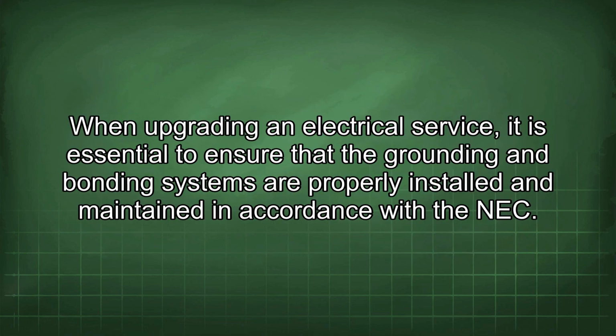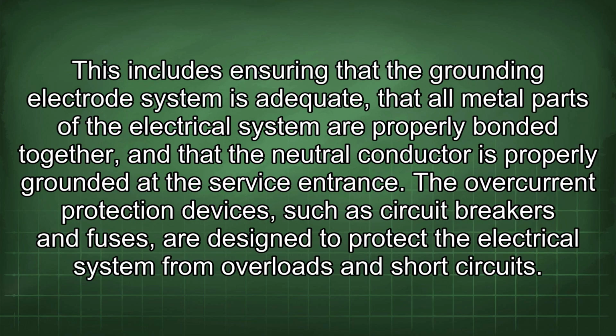When upgrading an electrical service, it is essential to ensure that the grounding and bonding systems are properly installed and maintained in accordance with the NEC. This includes ensuring that the grounding electrode system is adequate, that all metal parts of the electrical system are properly bonded together, and that the neutral conductor is properly grounded at the service entrance.